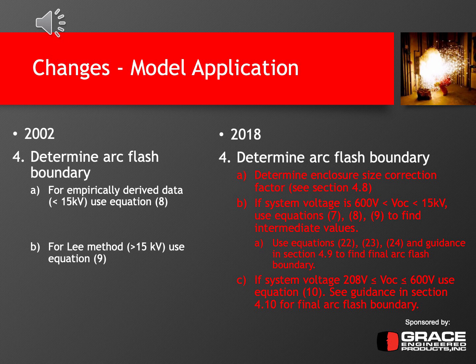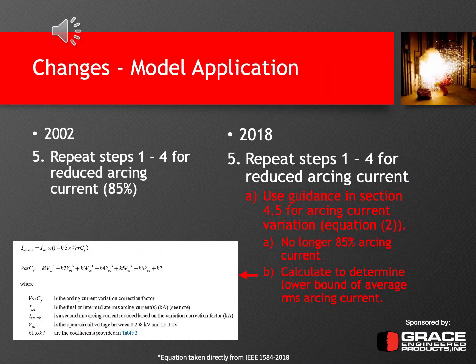And if the system voltage is again between 208 volts and 600 volts, we would use equation 10. Additional guidance is provided in section 4.10 for the final arc flash boundary calculation. And now the final step in completing the incident energy analysis at one particular location would be to repeat steps 1 through 4 that we just discussed for the reduced arcing current.